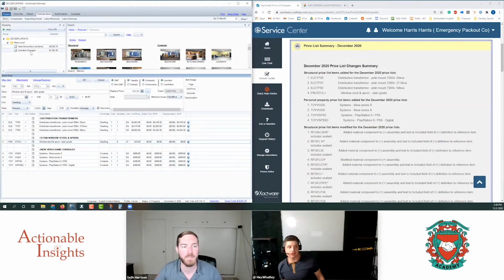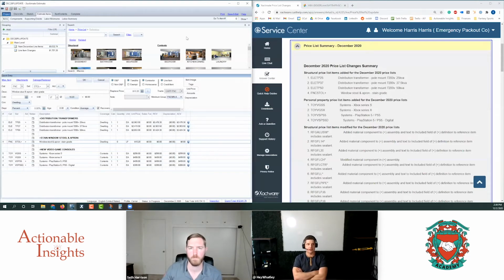Awesome. That's wacky stuff. Hey, just to circle back around on the distribution transformer, I pulled that up while you were going through this Xbox nonsense. Yeah, they have a bunch of the pad mounted transformers. I see like 12 of them here, but they're all for 480 volts. So those are the kinds that you see at the Yarrow Drive address in the warehouse that are pad mounted in a commercial environment. So the step down is 480 volt, and then that brings it down to 220 and 120 for our warehouse there. These things are, look, they're 7,200 volt. And so that's like the pole mounted. Yeah, you wouldn't want to be on the wrong side of that one. It's a lot of power, baby. Yeah, those are gnarlier for sure, but they definitely have those smaller ones, as one would expect. So anyhow. Thank you for doing some deep dive on that and getting some additional stuff up there.